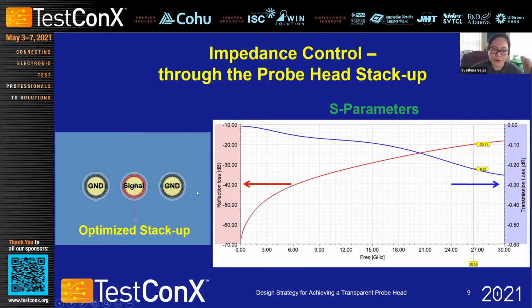When we optimize the stack-up, what we are doing is modifying the dielectric constant that the signal is in. That way we can modify the capacitance and move it up and down through design of thickness and spacing of the dielectric layers, which are the ceramic plates that provide mechanical support for the probe inside the probe head. All this can be done through simulations and through measurements to validate the results.